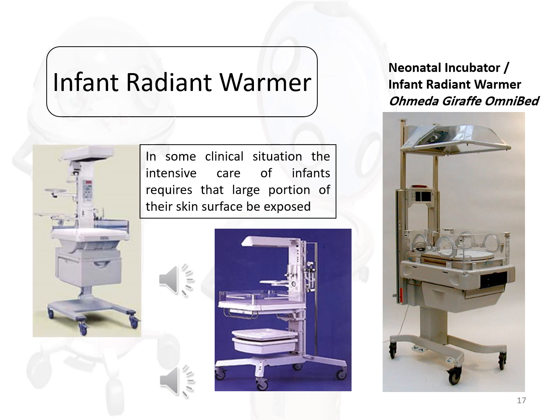A thermistor is placed on the exposed chest or abdomen of the infant to measure the skin surface temperature. The infant radiant warmer enables the clinical staff to observe the infant's condition, carry out a special procedure, and attach various therapeutic and monitoring devices. The infant is placed on a mattress under a radiant heating element. Low walls surround the mattress so that there is no risk of the infant falling off the device. The remainder of the area surrounding the infant is open to allow access to the patient.